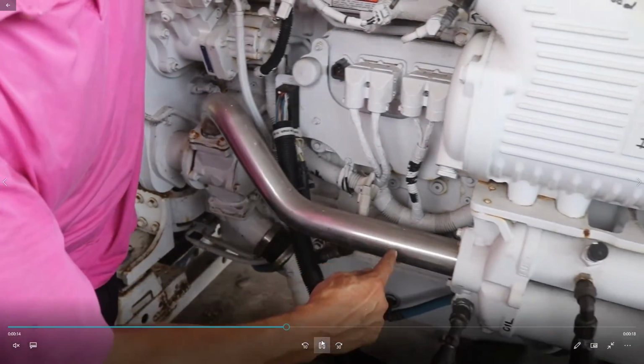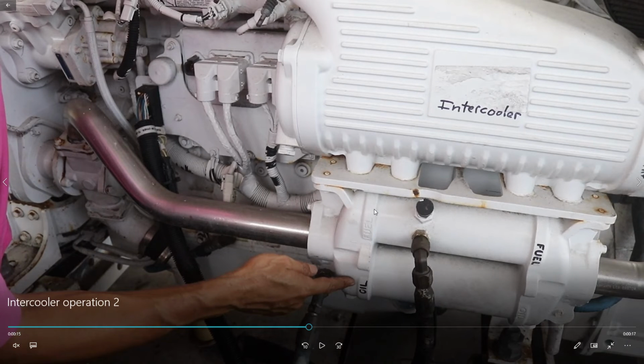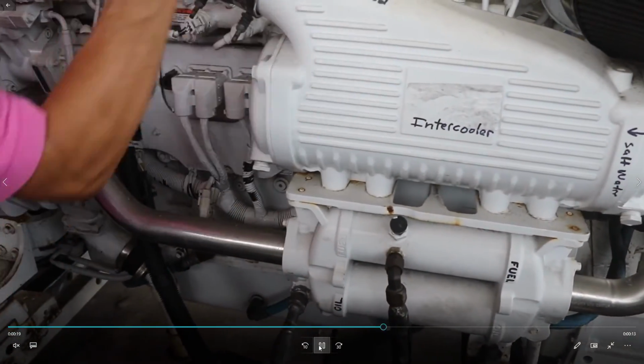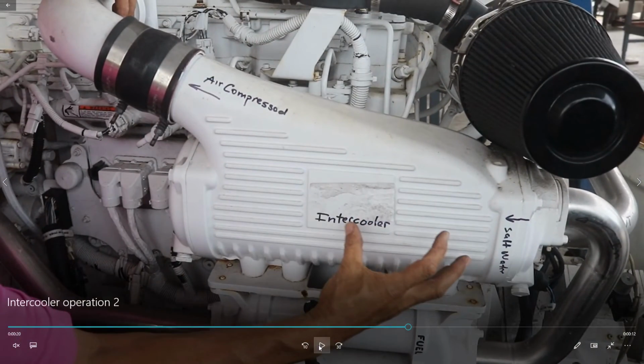The salt water enters through the raw water pump into the first two heat exchangers. One heat exchanger is the oil cooler, and the other heat exchanger is the fuel cooler. The raw water passes through the middle of both of them, cooling the motor oil and cooling the fuel. And of course, the salt water continues on the second side. All right? The salt water continues and enters the heat exchanger, passes through it and reduces the temperature of the air.